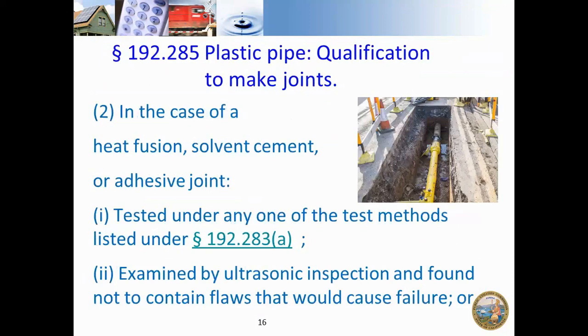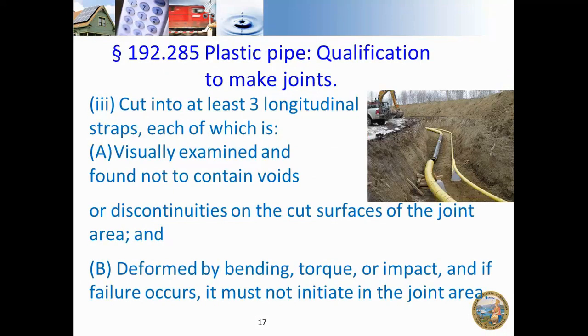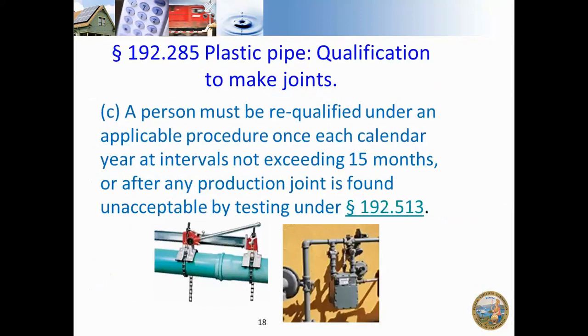Heat fusion, solvent cement, or adhesive joints are tested under any of the test methods listed under 283A. Ultrasonic inspection may also be used to ensure there is no failure. Testing also involves cutting into at least three longitudinal straps, visual examination, and deformation by bending, torque, or impact — any failure must not initiate in the joint area, meaning the joint is acceptable if it passes this test. A person must be requalified every 15 months maximum, or after any production joint is found unacceptable by testing under Section 513.